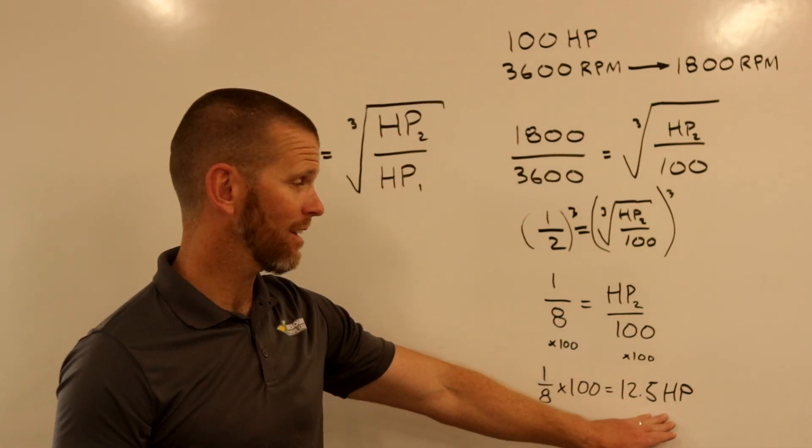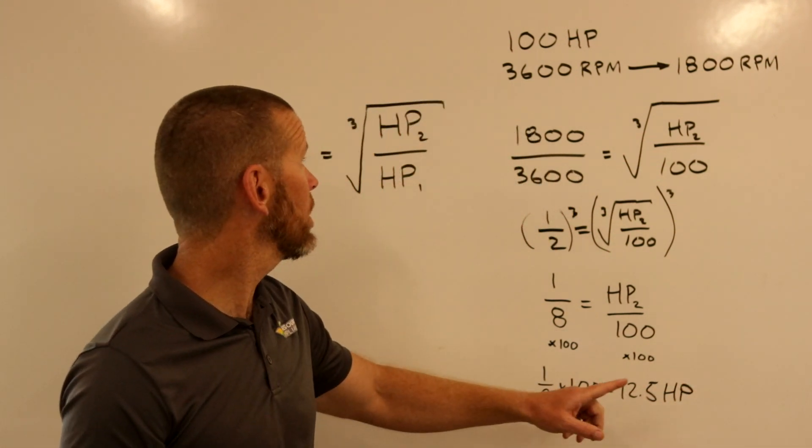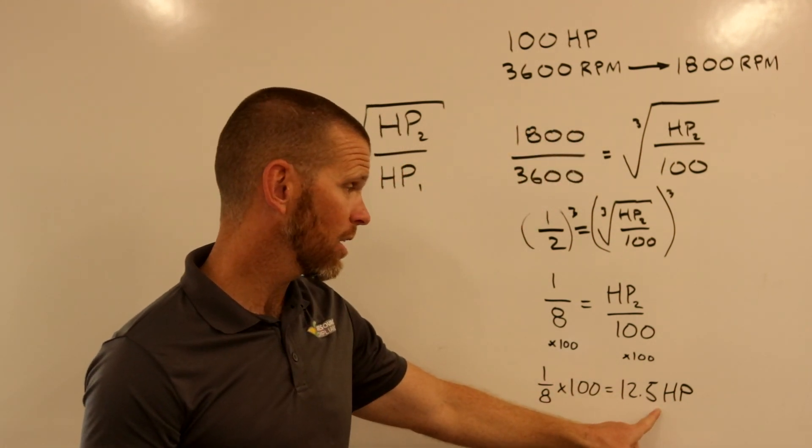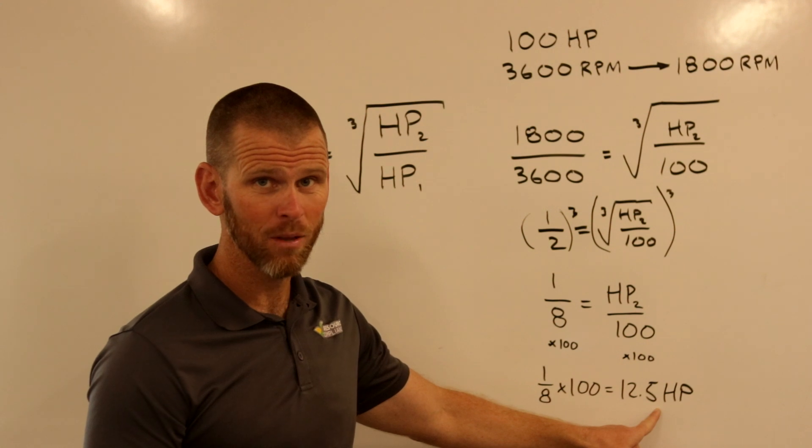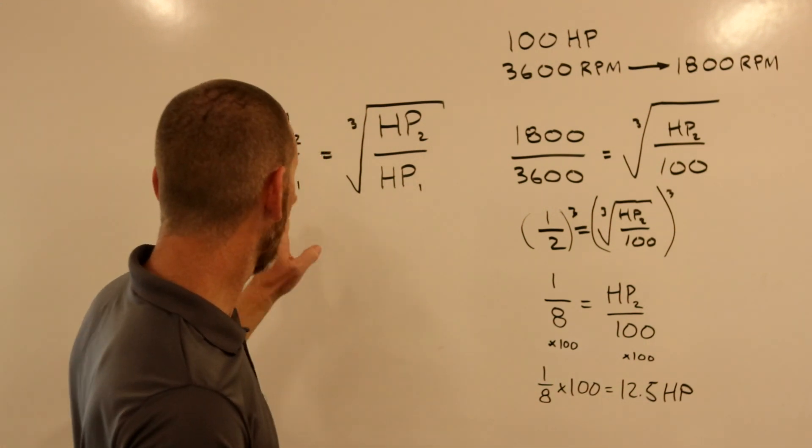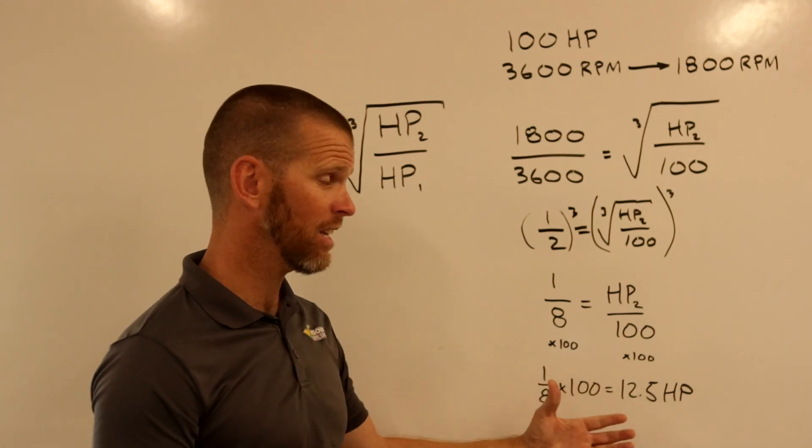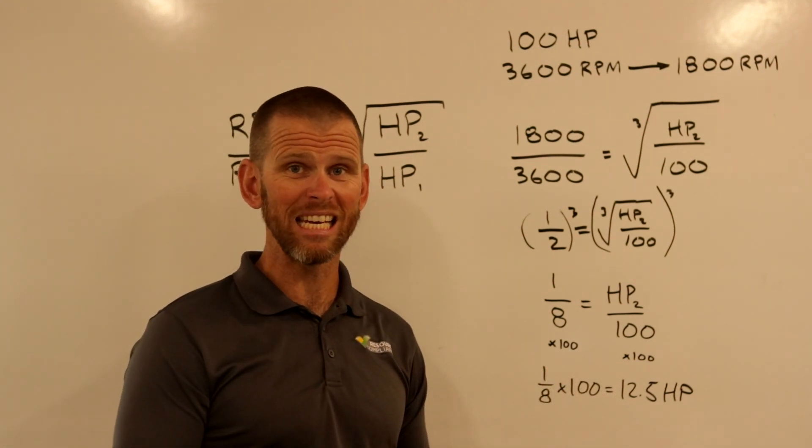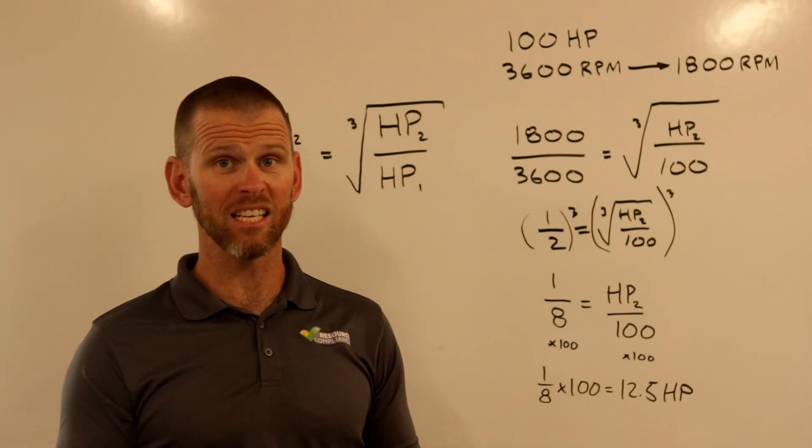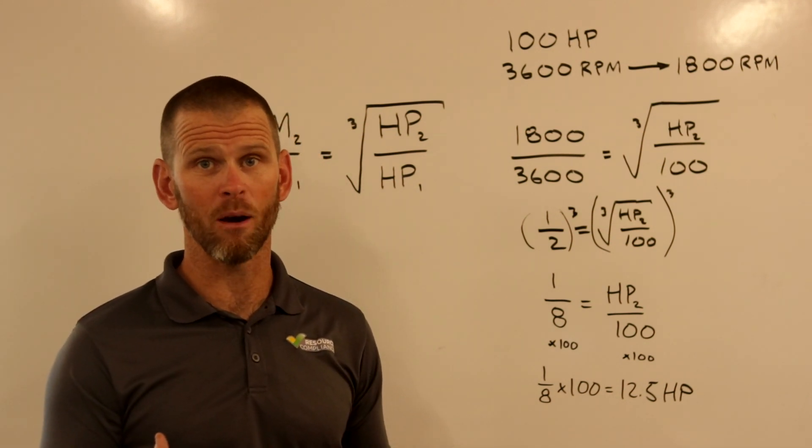So that is stunning. By lowering our speed by 50%, we reduced our power consumption to one eighth of the original power consumption. Our 100 horsepower motor is only utilizing or only needing to use 12 and a half horsepower. So there will be significant energy savings, cost savings in operating that way.